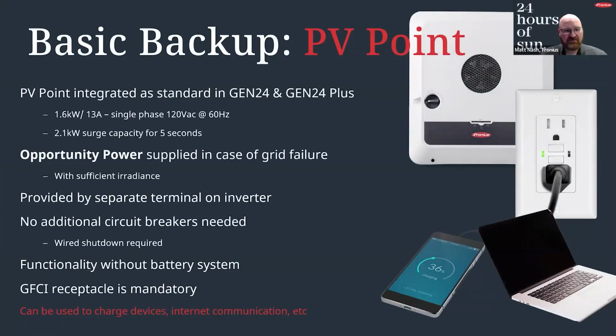So the Gen24 does come with basic backup right out of the box. This is our PV Point. So with sufficient irradiance on the array, you will be able to have up to 13 amps at 120 volts AC with a 2.1 kilowatt surge capacity for those higher inductive loads. So it's opportunity power.